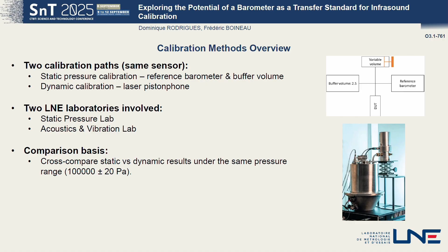by using a laser pistonphone, a device that we developed specially for calibration of infrasound sensors, in part during the Infra-UV project. So one key point also here is that to provide an accurate comparison basis, we asked the Static Pressure Lab to calibrate the barometer in a similar linear range to the one used in infrasound. So typically only 10 or 20 Pascal. So we asked them to calibrate the sensor at plus or minus 20 Pascal around the atmospheric pressure, which is approximately 1,000 hectopascal close to Paris.